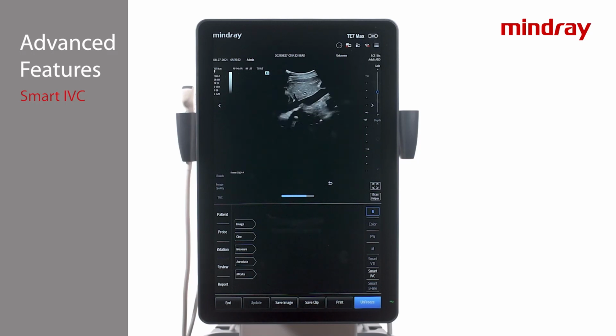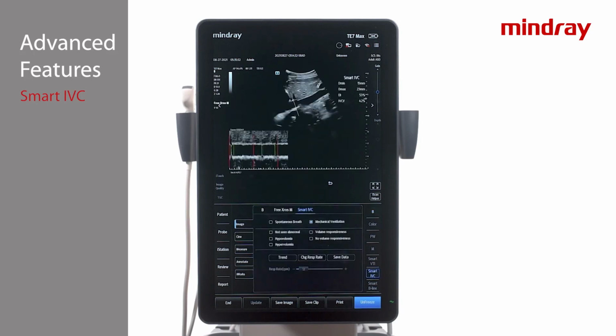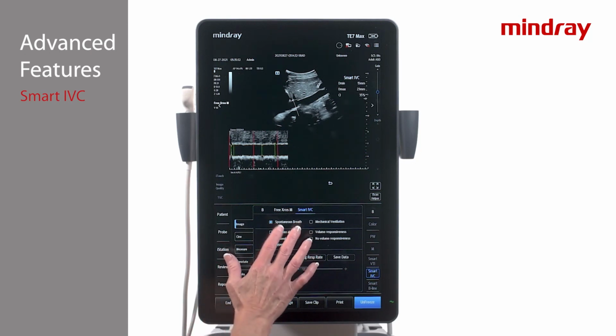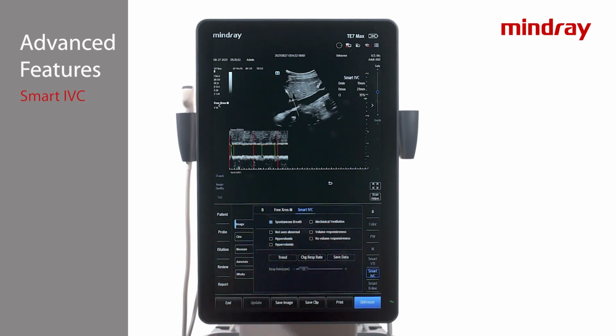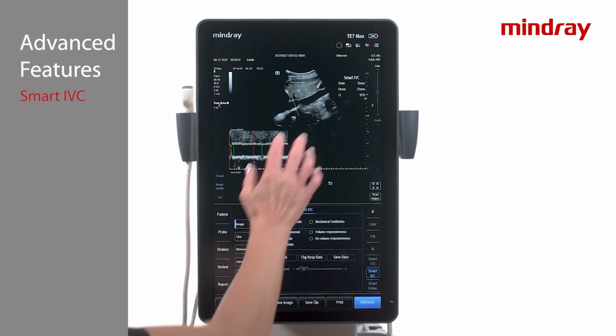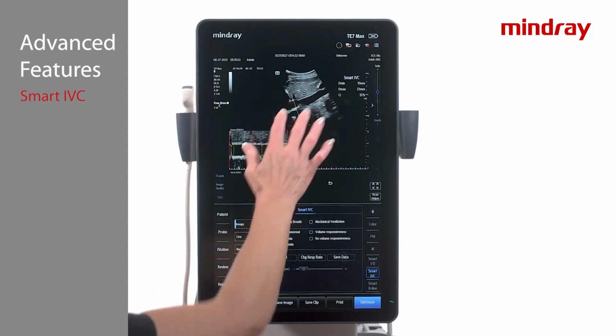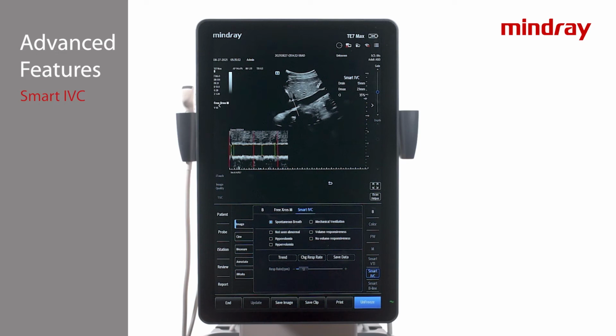The system will automatically locate the IVC target area, track and measure the change in IVC diameter. Select spontaneous breath or mechanical ventilation, which is located in the lower middle portion of the screen under the Imaging tab. If the sampling position is suboptimal, press the Edit Line tab. This will allow for modification of position and angle of the sampling line.